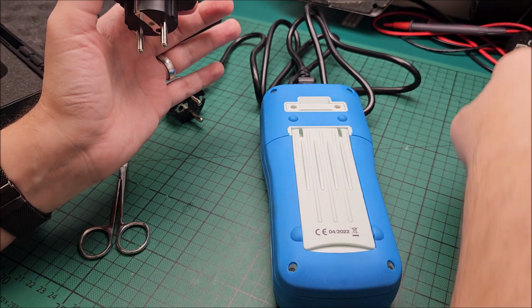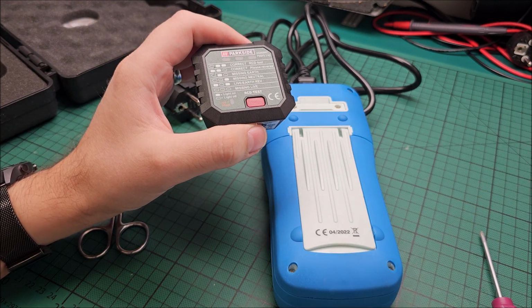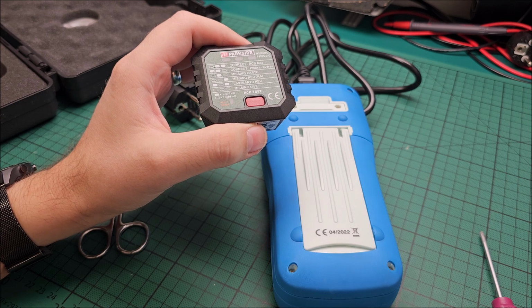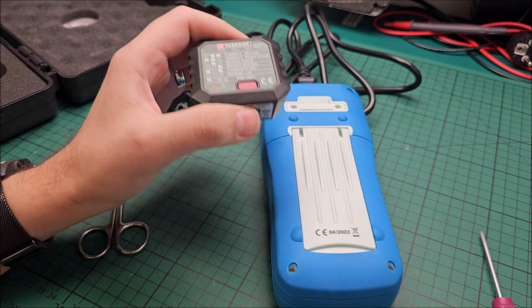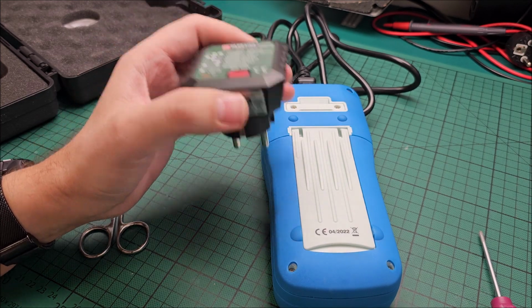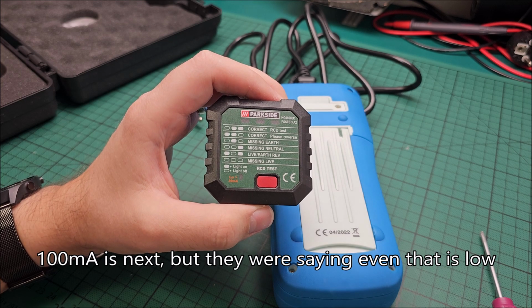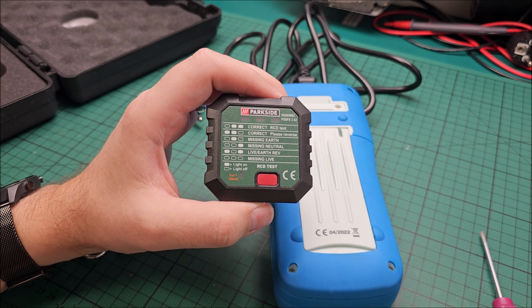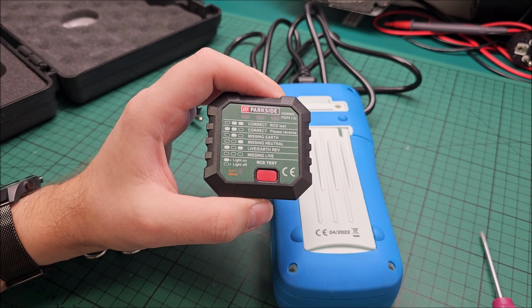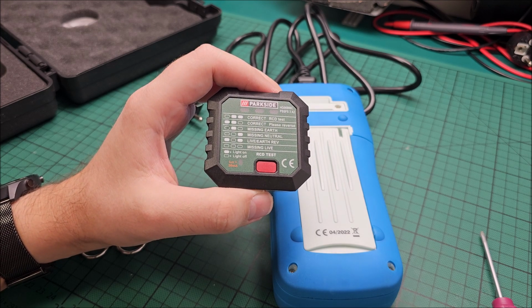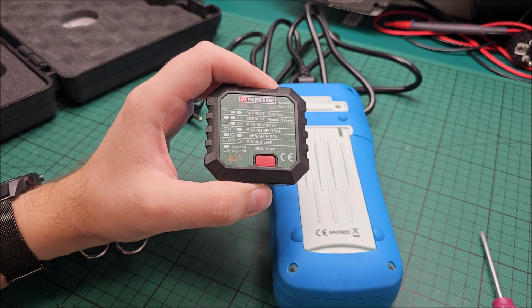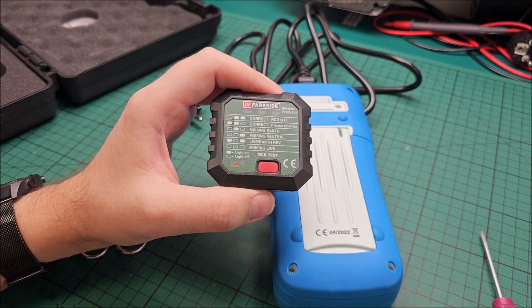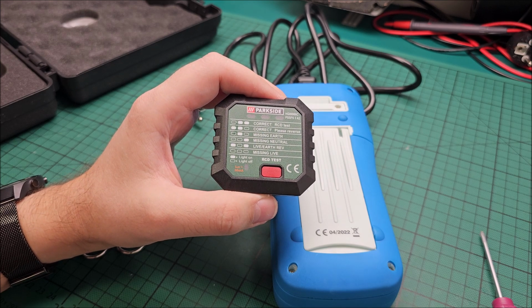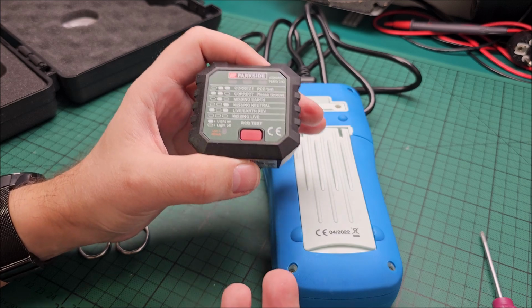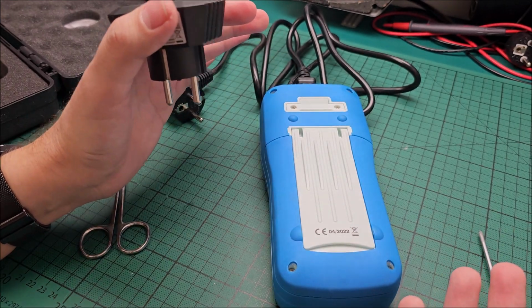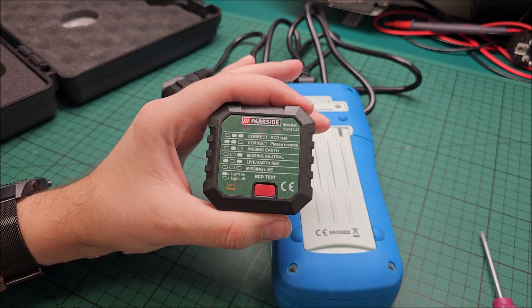A bit of weirdness. And I also asked a bunch of electricians, and all of them were, but why do you have 30 milliamp on your whole house? That's too low. You should have, I don't know, 300 milliamp or 150 milliamp. I'm not sure which is the next value. And I was saying, but it's not tripping by itself. I have appliances that I keep in good working order. I don't have leakage currents willy-nilly adding more than 30 milliamp to trip my RCD. So I have a low value RCD and everything is working absolutely perfectly. But all the electricians that I asked, obviously there are many more that know what they are talking about, but the ones that I asked were continuing to give the same answer.